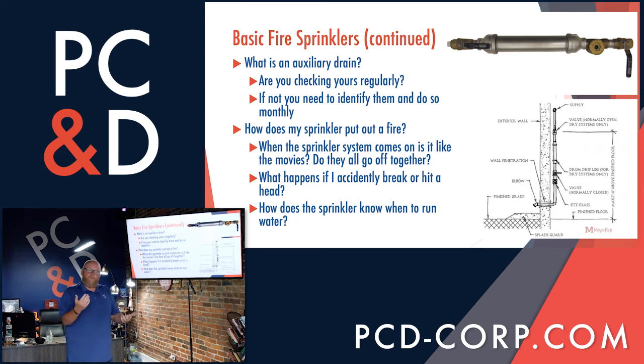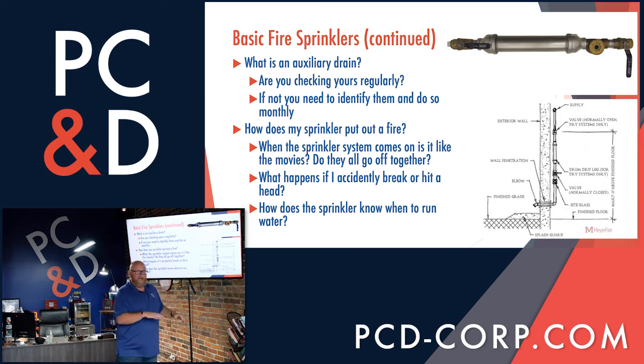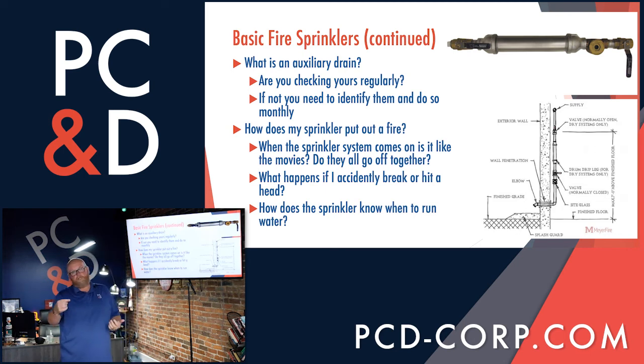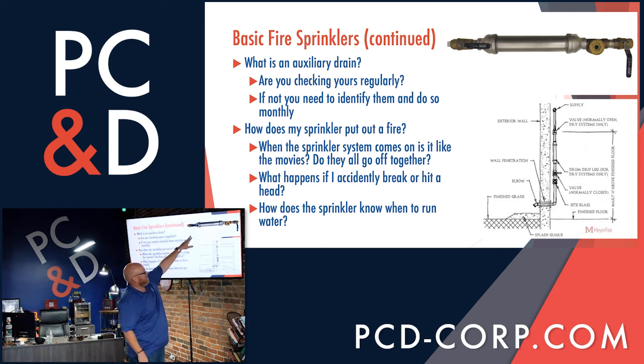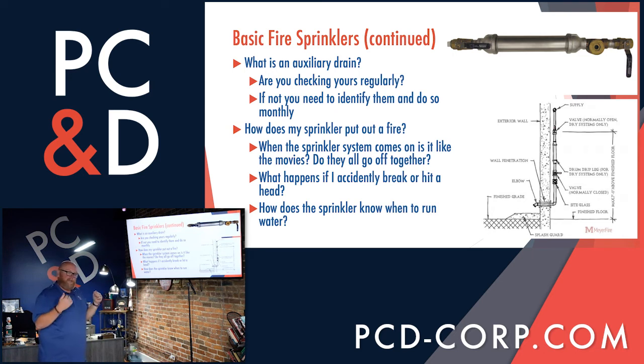So how do you keep that water out of a dry system? You do that by something known as low point drains, okay? So throughout your building, you are going to have several low point drains. This picture here at the top is what a typical low point drain will look like. You'll have a piece of 3/4 inch black iron coming into one side, and another 3/4 coming into the other side. When these systems are designed, they are designed to pitch toward that low point drain. So if that situation takes place like we just described, that air, as it pumps into the system, turns to water and humidity, it's designed so that water will always work its way back toward a low point drain.